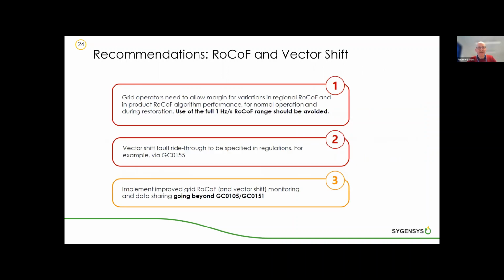So, recommendations in this area for rate of change of frequency (RoCoF) and vector shift. First of all, the system operator needs to allow for a margin for regional variations in RoCoF, rather than just assuming that they can work all the way up to the RoCoF tripping threshold. Vector shift ride-through, we believe, should be specified in the regulations, for example, by grid code modification 0155. And we think it would be helpful to improve monitoring of RoCoF and vector shift and sharing data beyond the current provisions, which are already very helpful in 105 and 151.